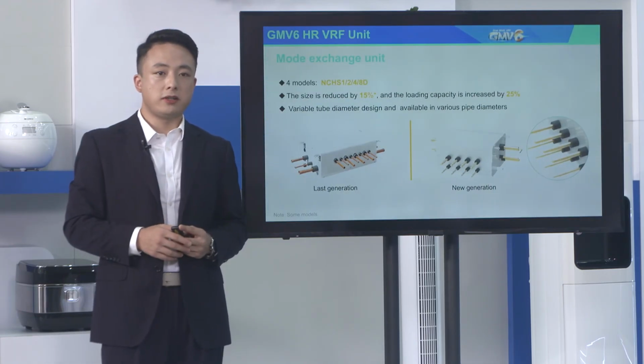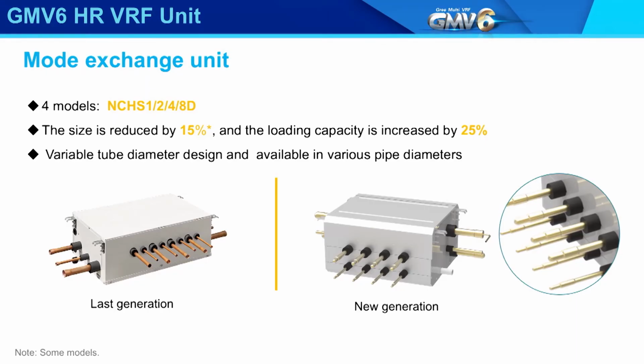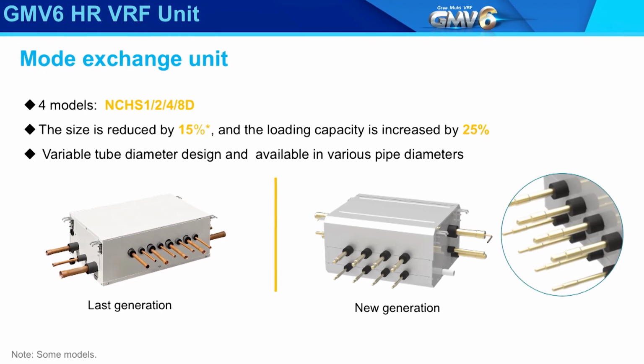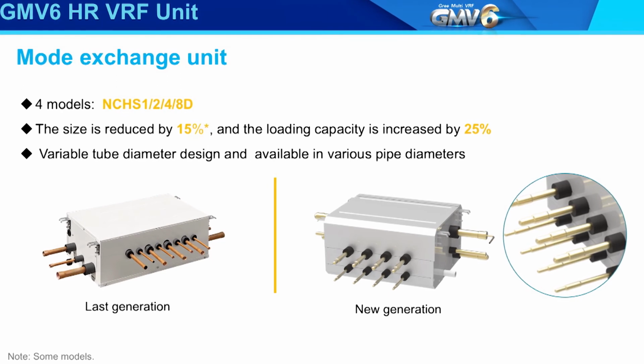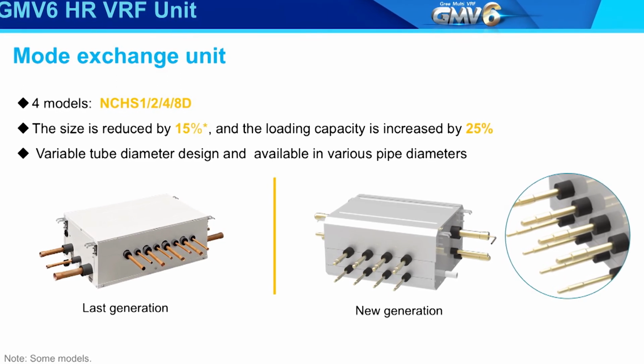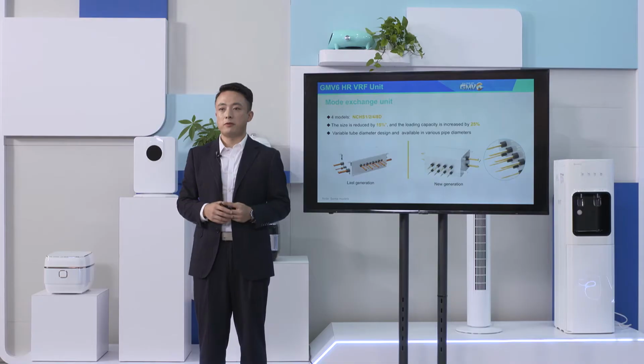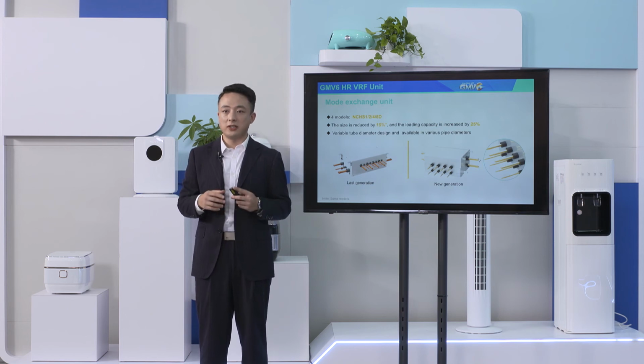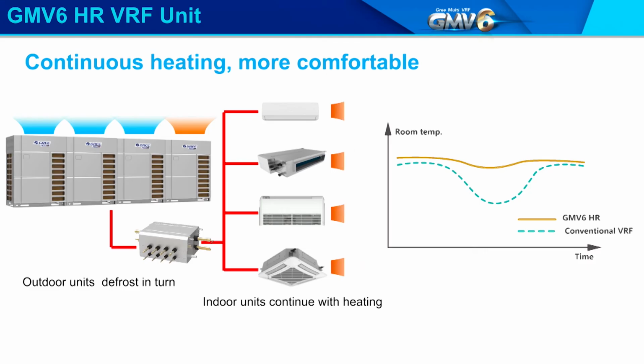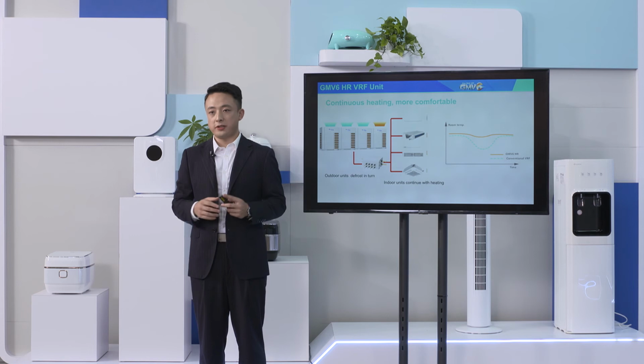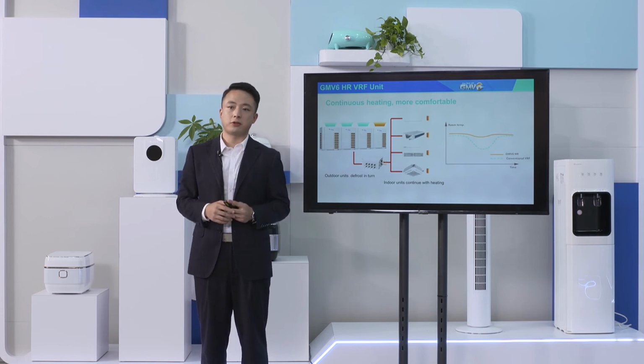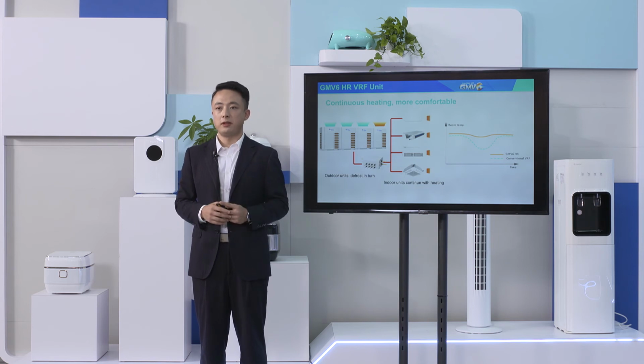Mode exchange unit is available for 4 units. Its size is reduced by 15%, and the loading capacity is increased by 25%. We adopt a variable tube diameter design for easy installation. Finally, GMV HR adopts continuous heating design. When the modules are combined, the defrosting can be rotated between the modules to reduce indoor temperature fluctuations and further improve the heating comfort of the unit.